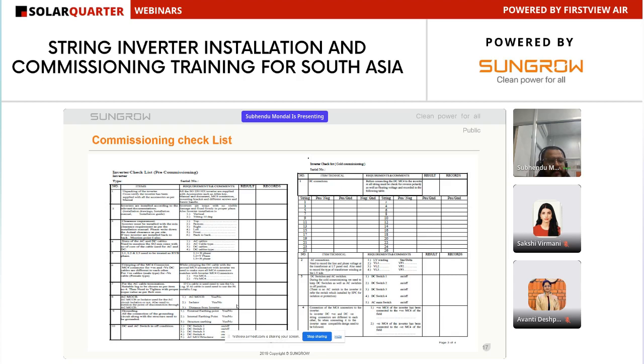So the first point is unpacking of the inverter. As I have already told, after unpacking we have to check whatever material we have received. If any material is not received, then we have to mention it. Then inverter installation: whether the inverter is installed vertically or with 10 degree tilting, we should mention that. Then ground clearance and inverter clearance.